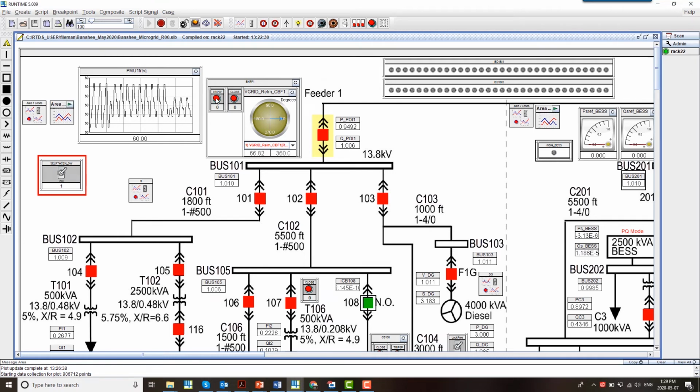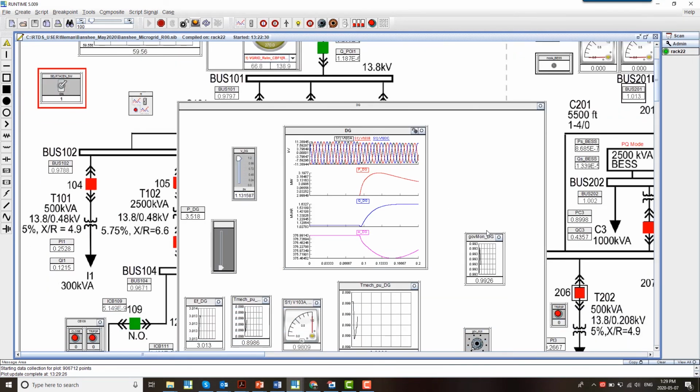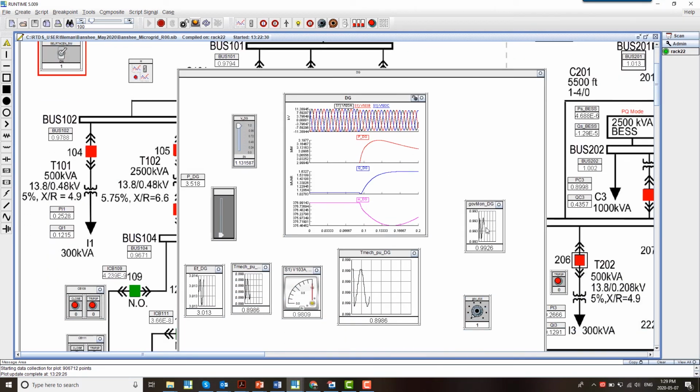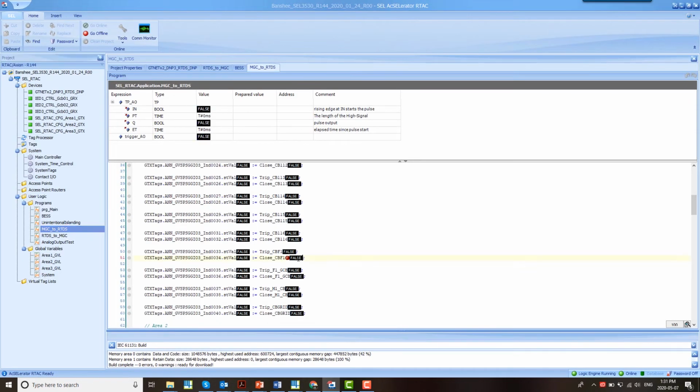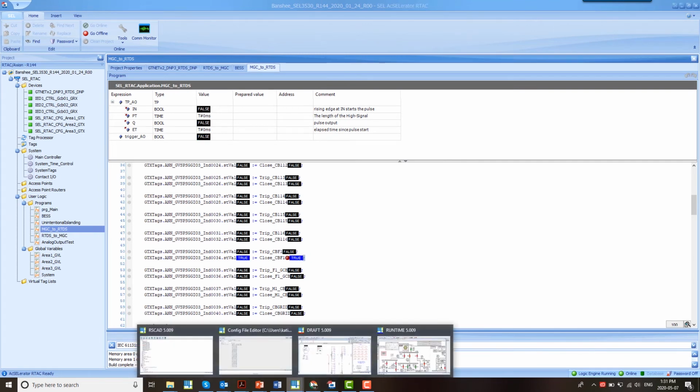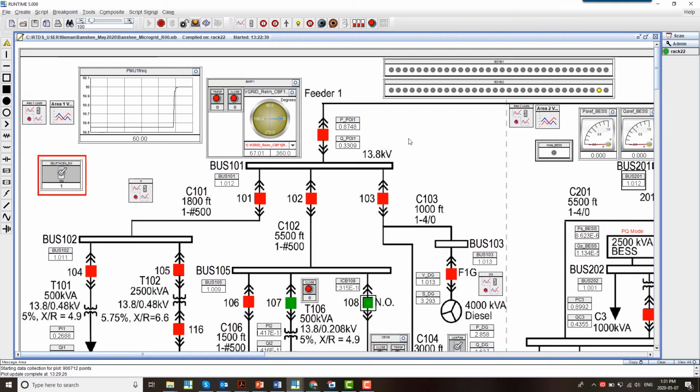Upon islanding, we can see the microgrid frequency begins to fall, and then load I2 is shed by the controller. The microgrid frequency stabilizes at around 59.6 Hz. The governor and exciter controls of our diesel generator have also actuated and changed the quantities of P and Q injected into the island. We can then reclose our Area 1 feeder breaker, either locally or via the external controller.